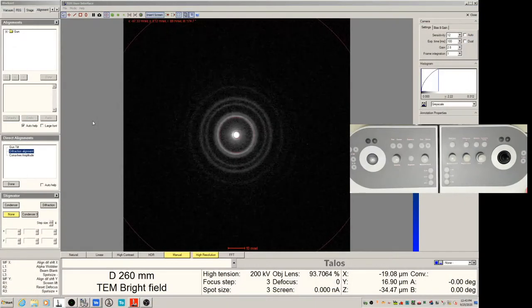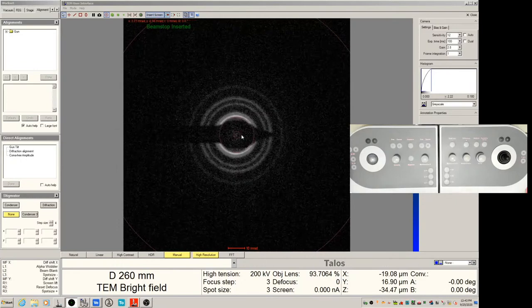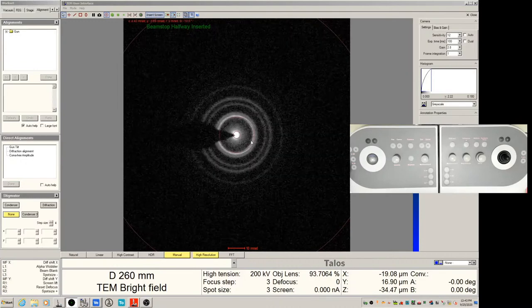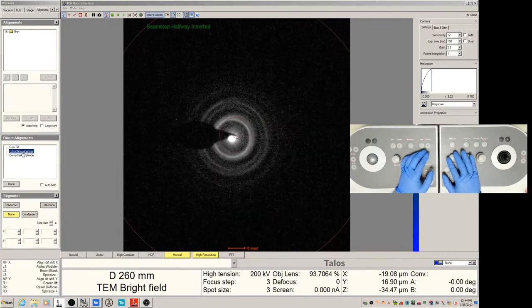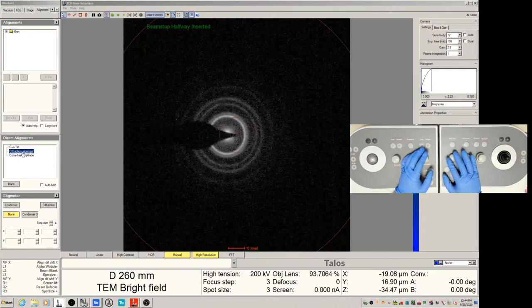That's when you want to use a beam stopper. The beam stopper button is controlled on the flu cam toolbar. So in here you can find this is insert beam stop, this is halfway insert, this is out. So right now it's out. So if you click this insert beam stop, all right. So now you can see the beam stopper. Right now it's inserted right here. Or you can use halfway insert. So it retracts halfway.